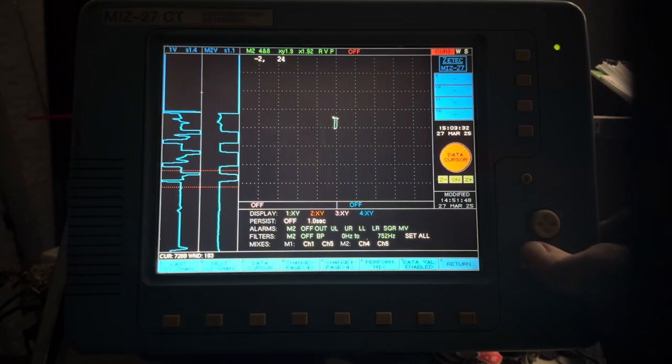So here you can clearly see, whether you're looking at absolute channels or differential channels, the total volume of the material that's missing is what is going to determine the amplitude of your signal. More metal missing, bigger impedance change, larger signal. So oftentimes, signal amplitude or voltage can be used to size the severity of flaws.